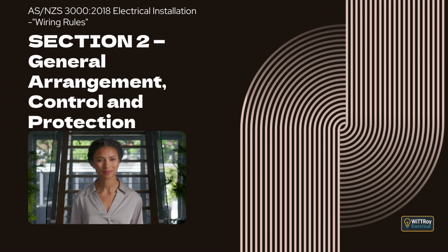Clause 2.5.3.4 Omission of overload protective device. This clause explains when overload protection may be left out entirely. One situation is when opening the circuit during an overload would create a greater danger than leaving the circuit energized. This applies to certain safety system supplies, lifting magnets, or some machine excitation circuits. Where this happens, an alarm system or monitoring device may be recommended instead of automatic disconnection.